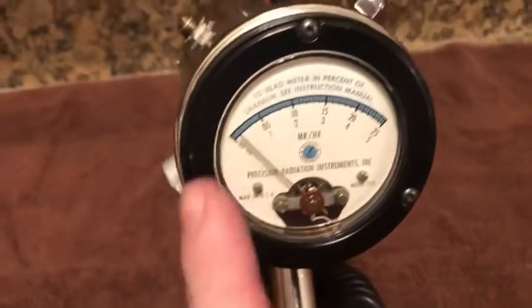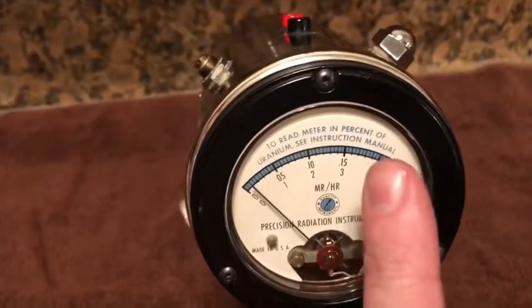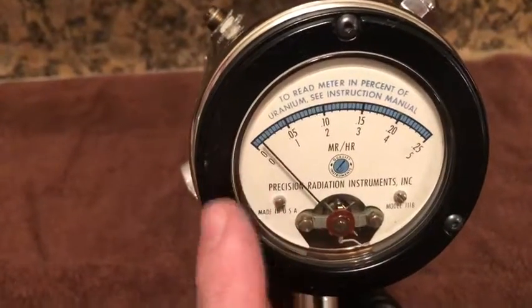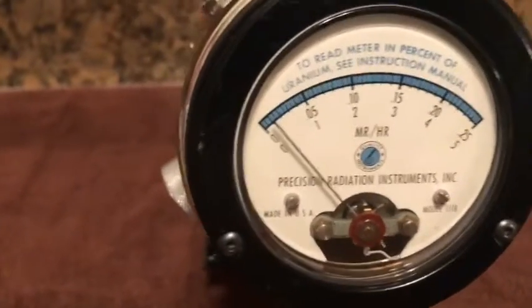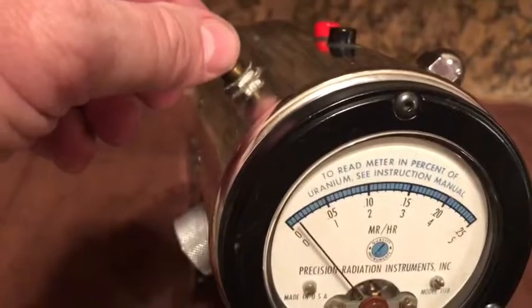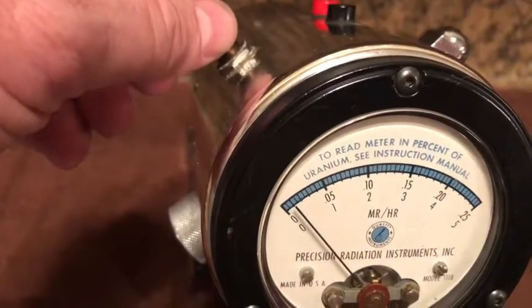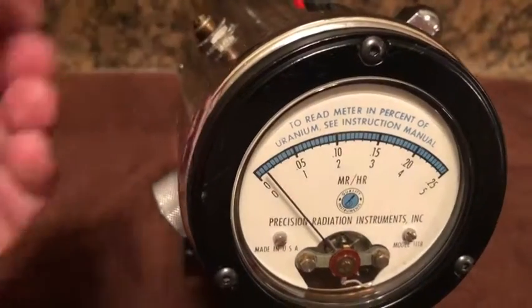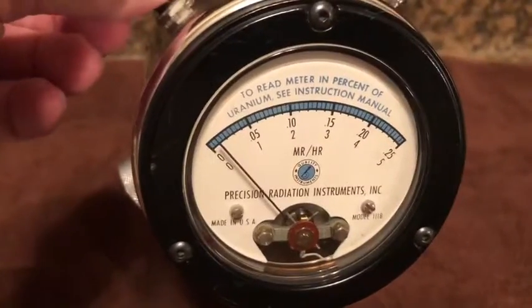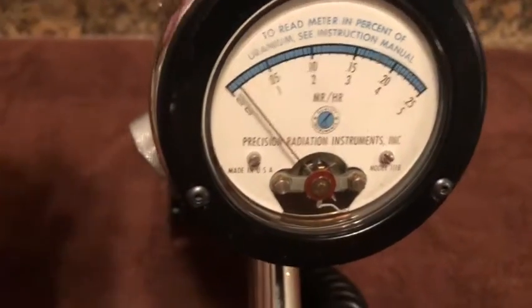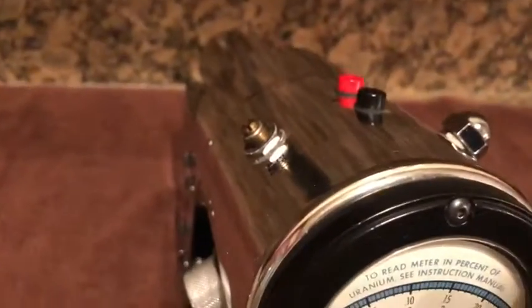When you turn it on, the meter should deflect and then settle back down towards the 0. If it doesn't go all the way down to the 0, you can take a small screwdriver and adjust this so it goes down to the 0. Or if it's below 0, you can adjust it to make it go back up to the 0 and align it. It's pretty self-explanatory. You won't have any issue with that.